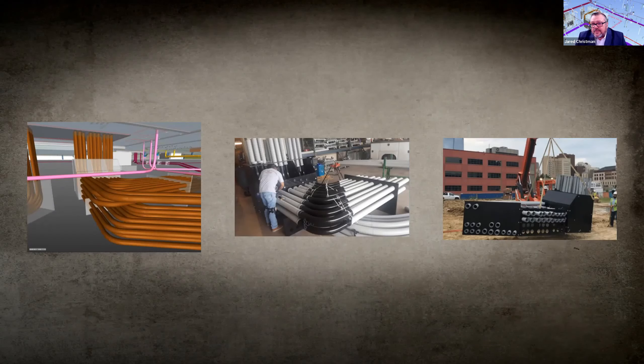And on this final image, this is a pre-assembled underground assembly. This was one of those rare Texas summers where we got considerable rain and they kept having to close down the job site due to flooding. So instead of just pulling off the electricians and having them idle, we brought them all into the prefab shop. They built these assemblies based on our model and shop drawings, stored them in the parking lot until the job site opened back up. As soon as it did, we loaded them on a truck, got them out to the job site, put them in the trenches, and we ended up saving approximately 16 days off of that delayed schedule.